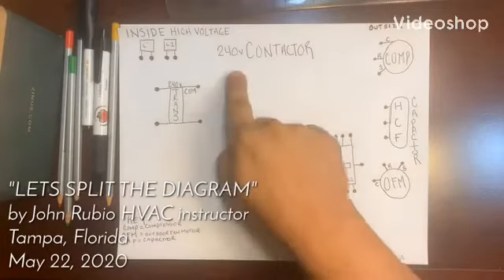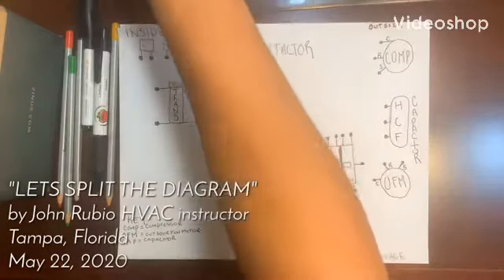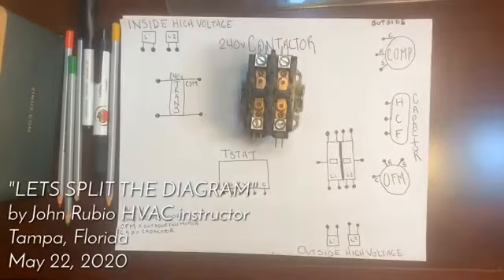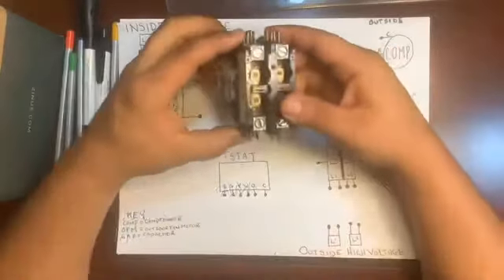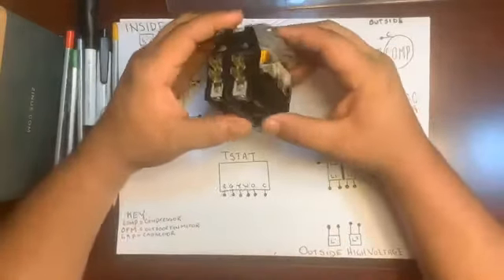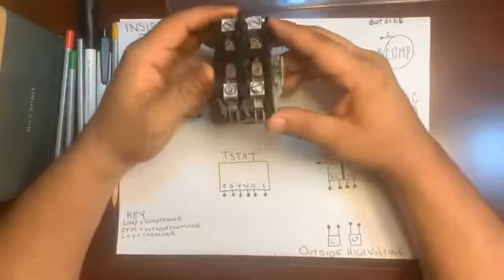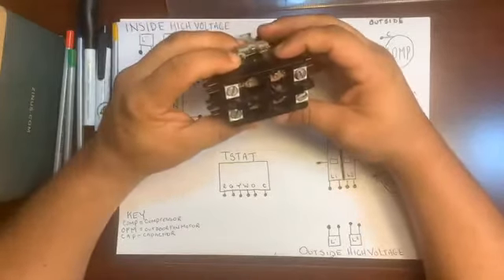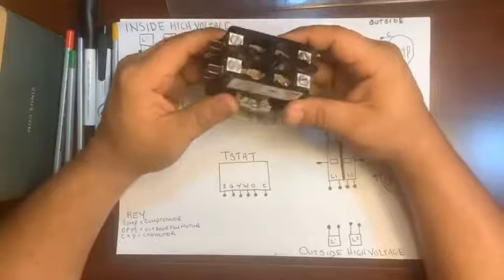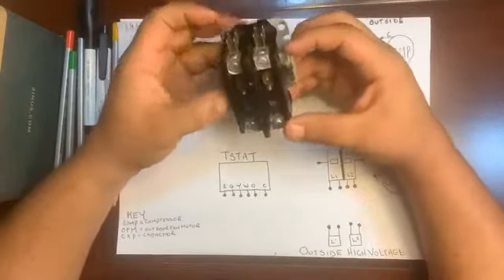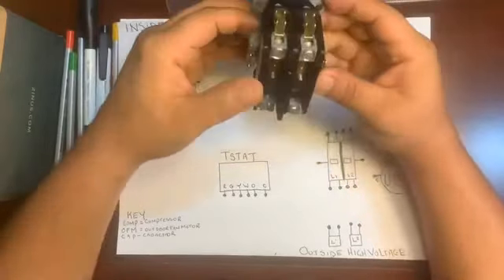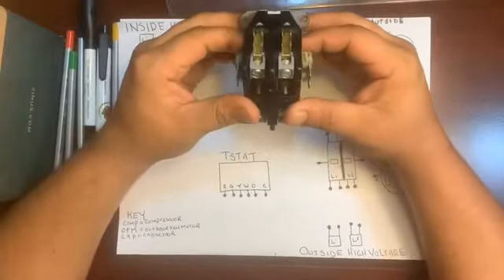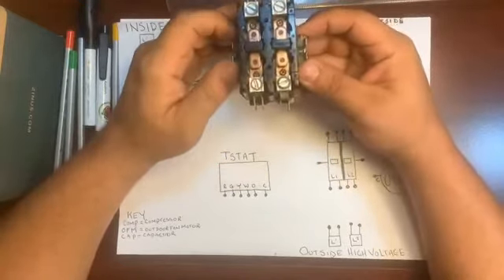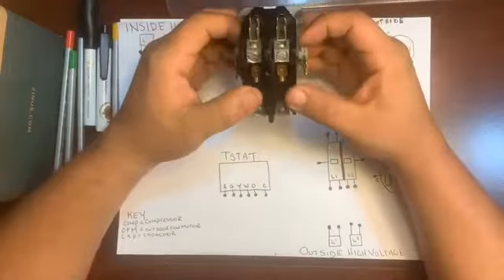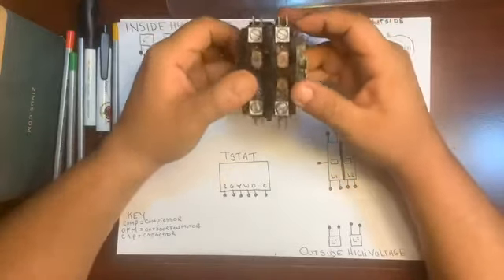We're talking about the 240 volt contactor. This relay right there is the relay that you will find in every condensing unit of every air conditioner that you work on. Absolutely, especially residential. It goes in the condenser every time. So this is a condenser relay that goes in the condenser and activates the compressor and the compressor motor.